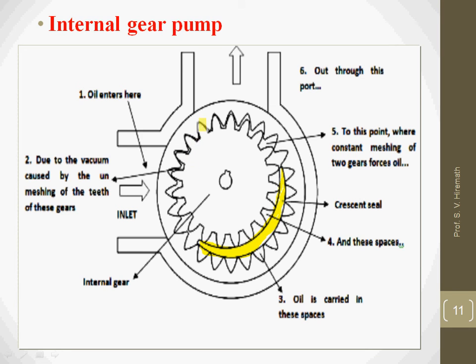See here, from this point, if you observe, there is an increase in the volume because the teeth are going to be in an unmeshed condition, right? Because of this unmeshing there is an increase in the volume, and this increase in the volume is going to reduce the pressure.